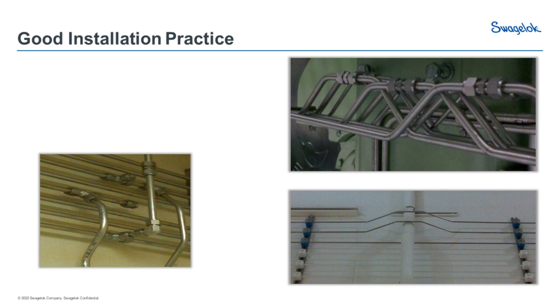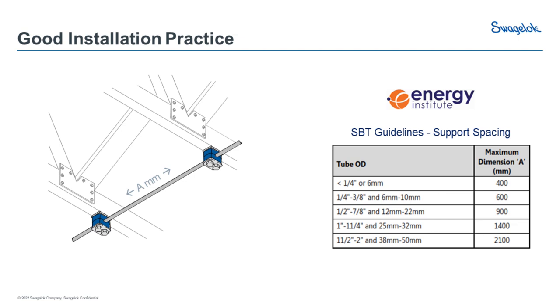At the top right you can see what you could almost call maintenance loops — some people use these for maintenance so they can get in, gap check, leak check, and get access to fittings without getting wrenches too tangled up. This also allows for thermal expansion and some movement, same as the picture below it. At the bottom left, we've got a bunch of different ways to break out of a tube system — some nice loops and then perhaps a little simpler, using a tee or an elbow. If your tube wranglers aren't that great, luckily there's pretty much a tube fitting out there to put in the system to get you where you need to go.